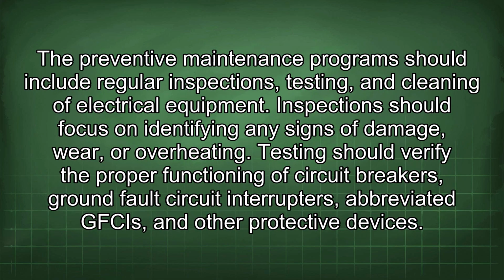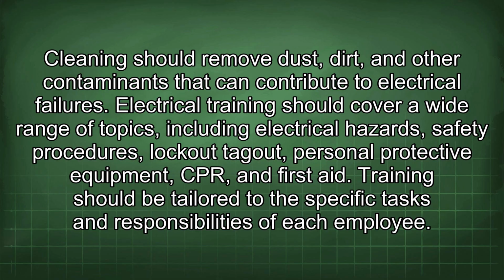The preventive maintenance program should include regular inspections, testing, and cleaning of electrical equipment. Inspections should focus on identifying any signs of damage, wear, or overheating. Testing should verify the proper functioning of circuit breakers, ground fault circuit interrupters, abbreviated GFCIs, and other protective devices. Cleaning should remove dust, dirt, and other contaminants that can contribute to electrical failures.